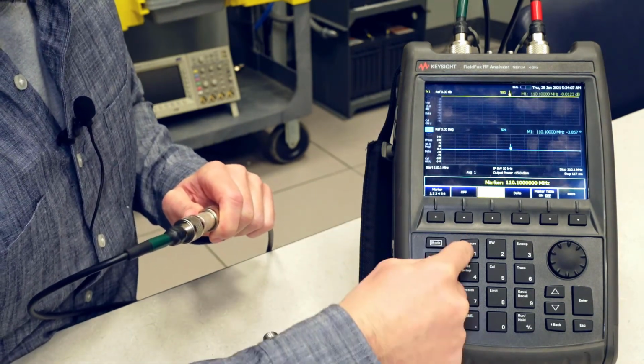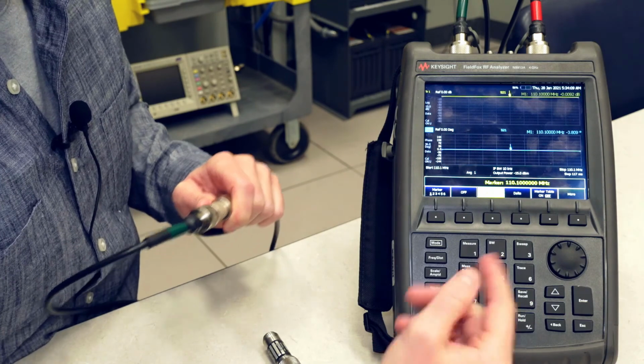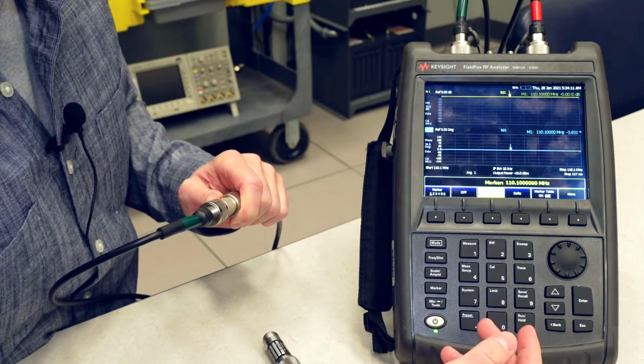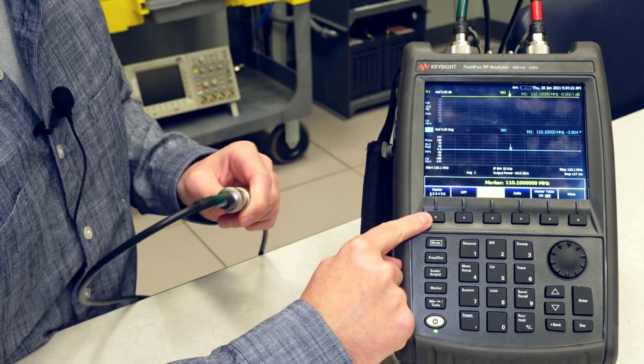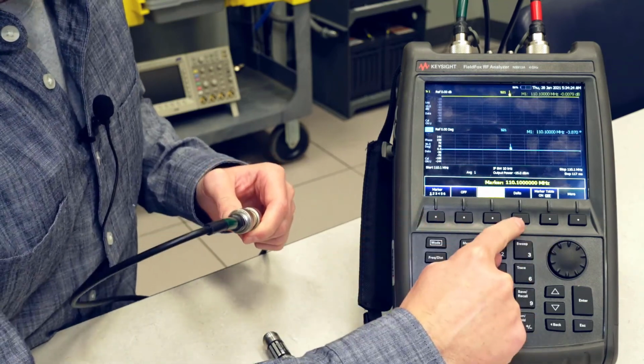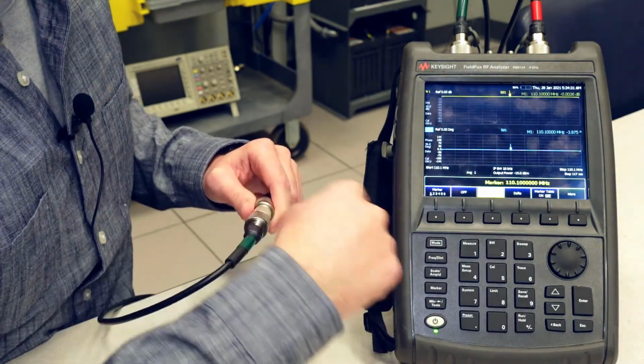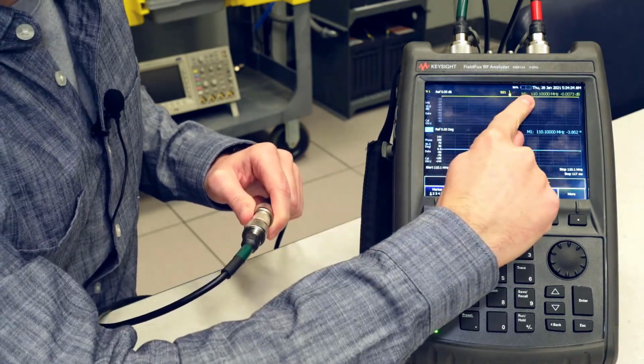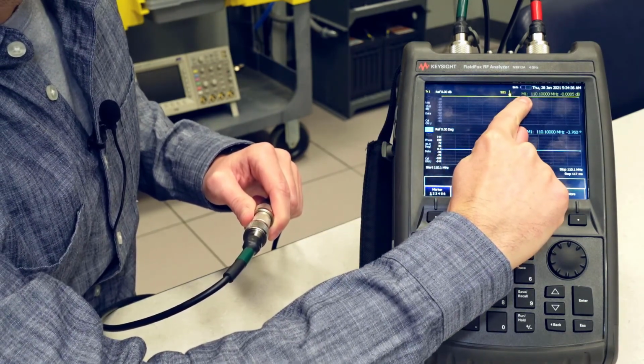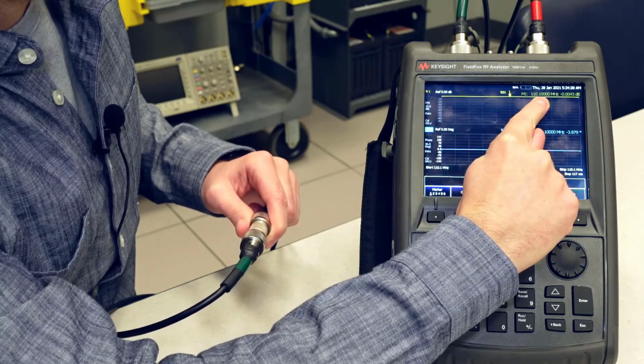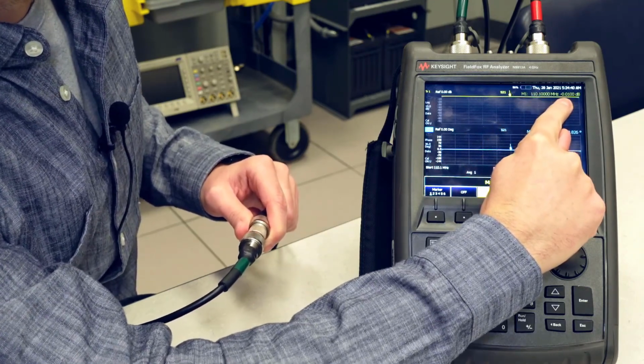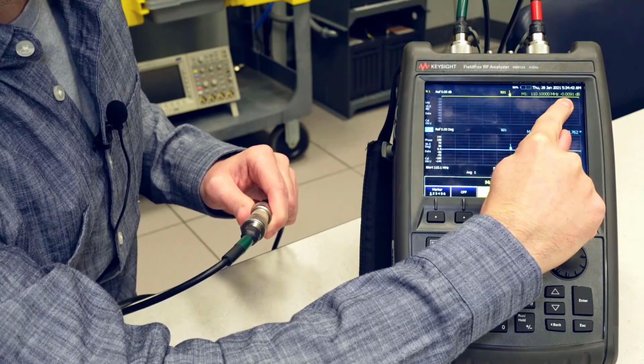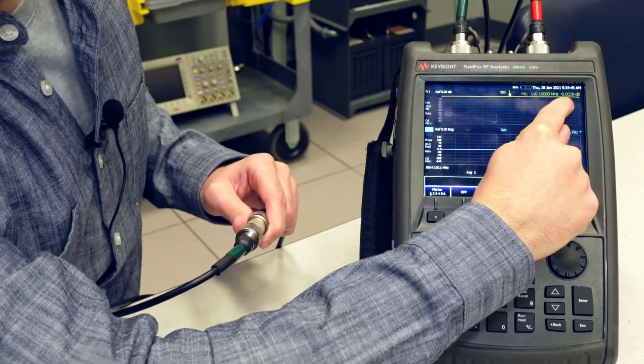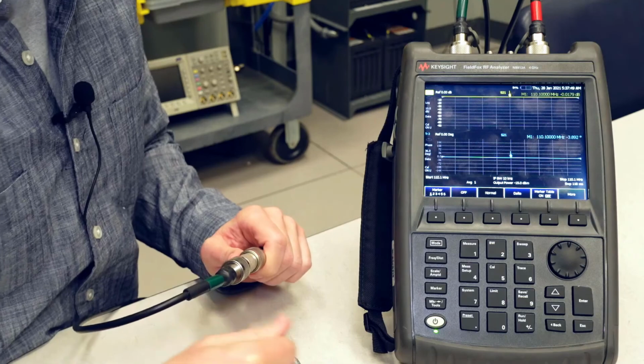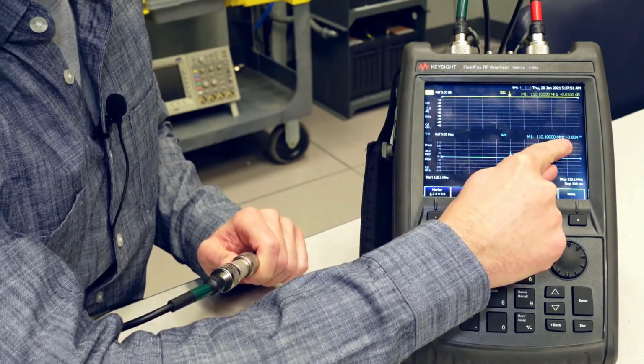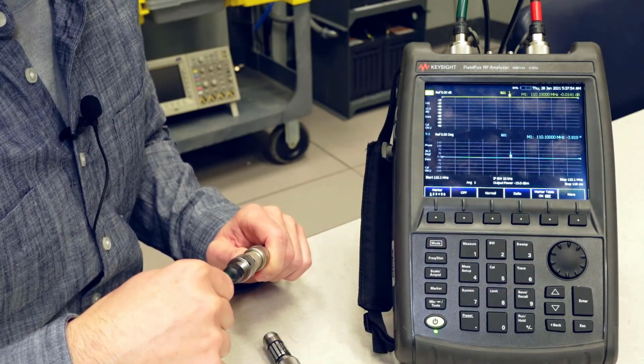If we wanted to change that, we would just key in a new marker using the number keys. You have several markers that you can add to the traces, as well as marker delta options. We can see with our normal marker set, on the top right of each trace, M1, 110.1 megahertz. I'm reading a very small amplitude here of 0.009, and that's pretty much 0. And we can see here that we've got negative 3.8 degrees for the phase trace.